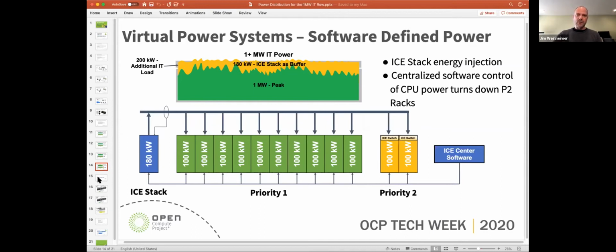The controlled devices here can be in-rack devices, smart circuit breakers, intelligent power shelves, or almost any other network connected device that's capable of limiting or switching load. And the important part is the control of these devices to maintain the high SLAs on the priority one equipment. The power control software here is also providing feedback to the software stacks running on these racks to be able to shift load in the cases where the primary racks are at peak draw and no additional capacity is left for the priority two racks consistently enough to keep them online.